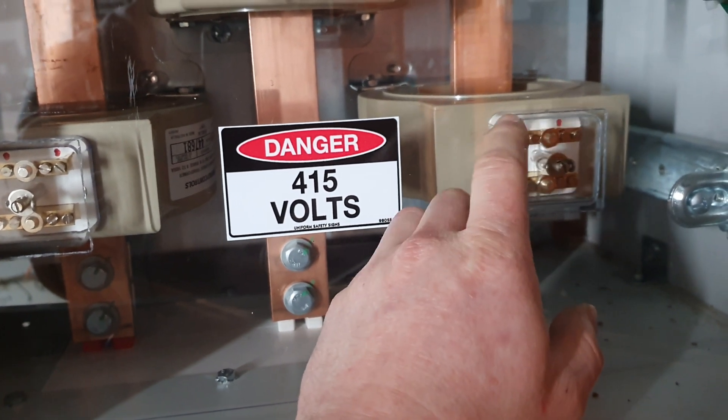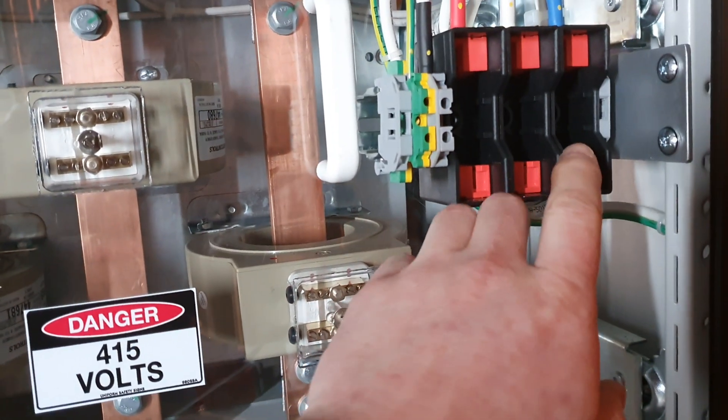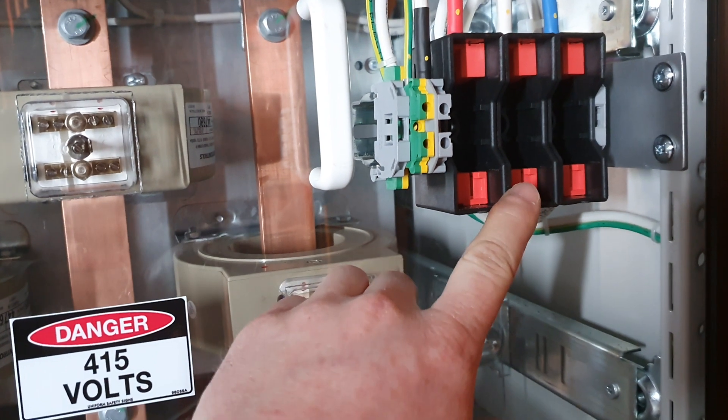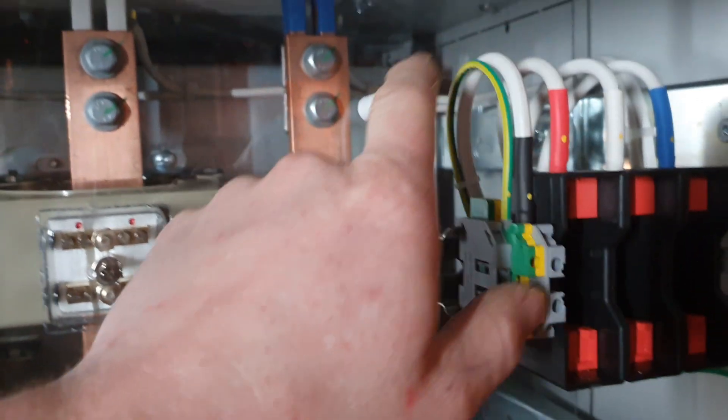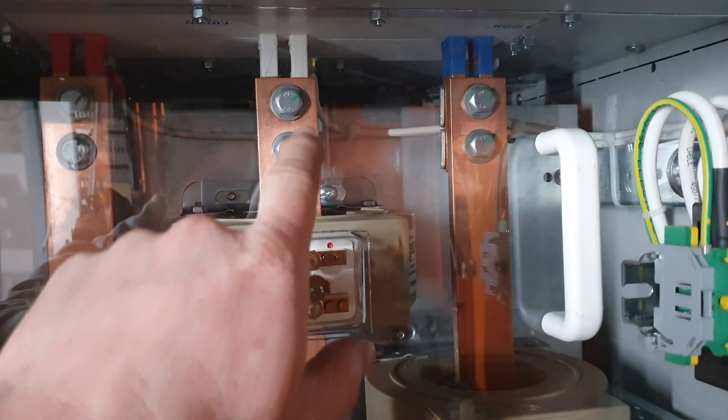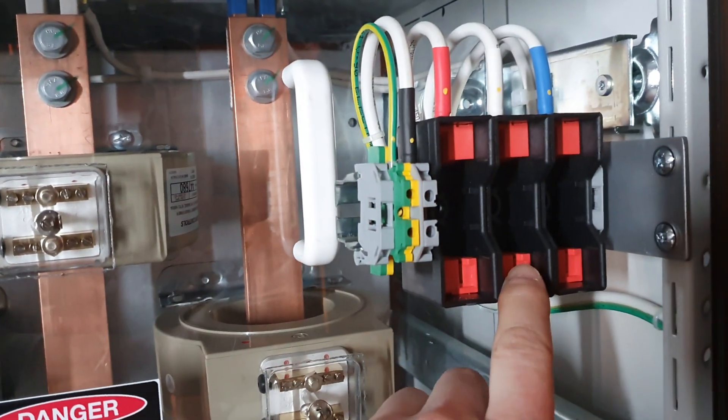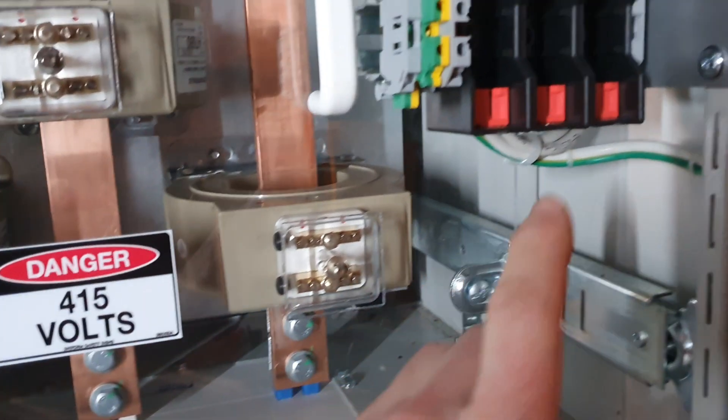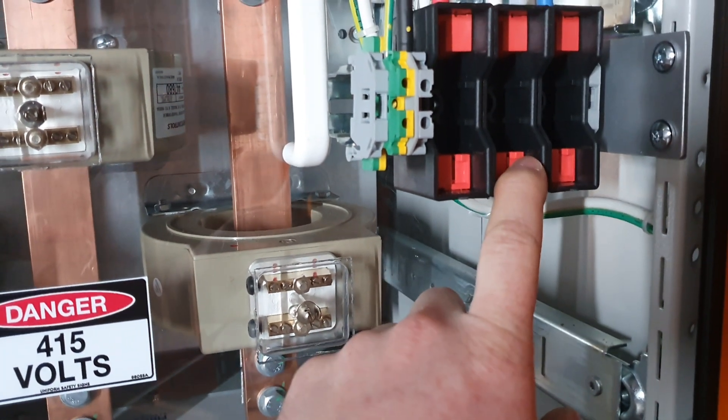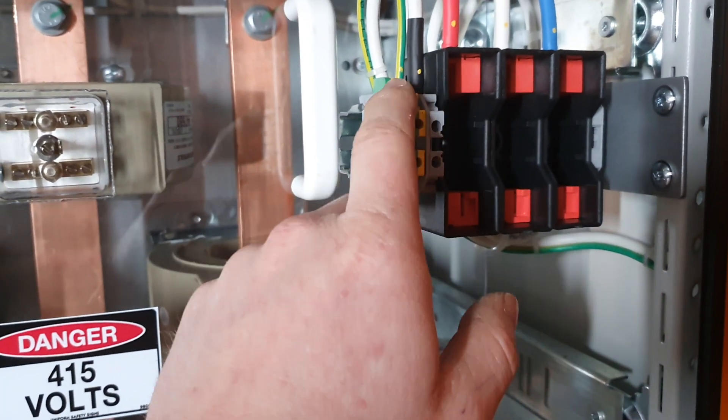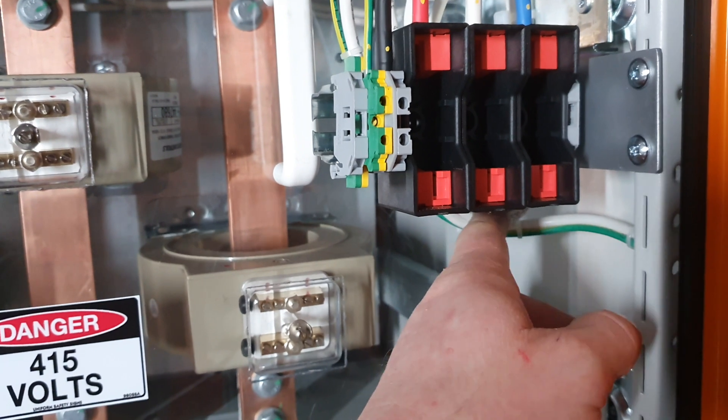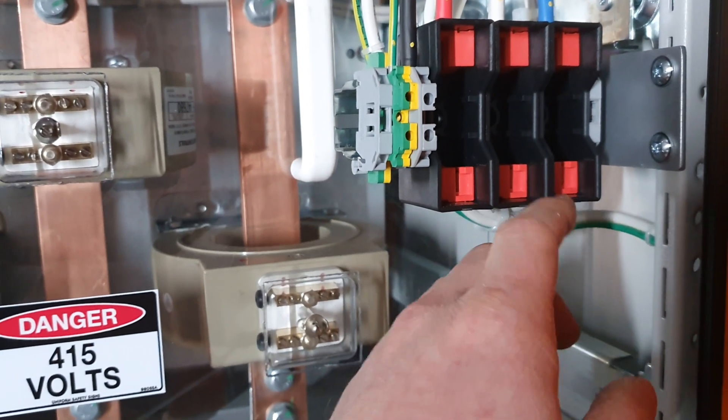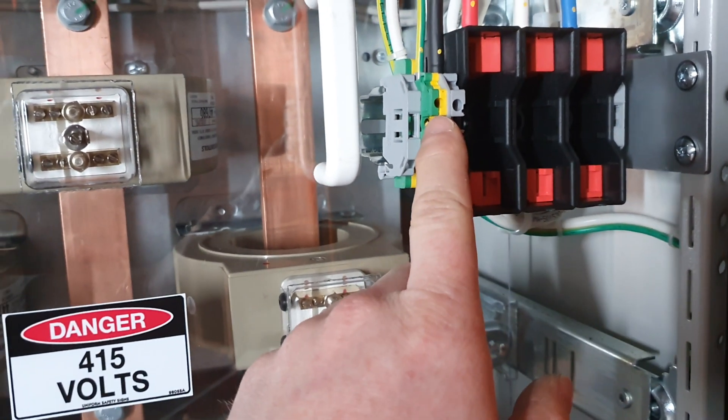And then you've got fused voltage. So if you watch, four of these cables they go in, they actually clip in behind here so that's a voltage. You need the current and the voltage to make this work. And then you've got a neutral and an earth. So three of the cores of this cable go into the phases, one for the neutral, there's an earth core and then the other six hook onto these electromagnets essentially, sensitive electromagnets.